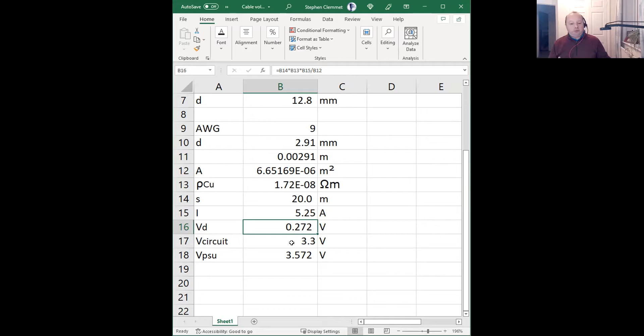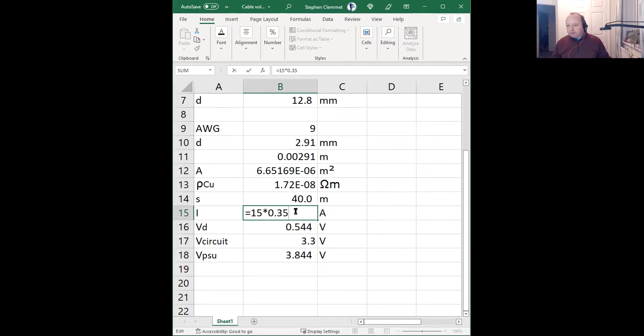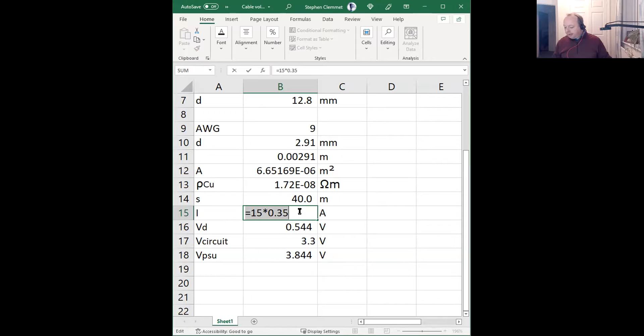And so look, we can just see here, if we make this 40 meters - make that 40, fingers crossed - things start to get a little bit more ugly. If we up the current... what have I done there? Oh right, that's something else, I remember that now - just experimenting with it. Yeah, if I up the cable to say 30 amps, then the longer the cable and the more voltage and current we want to put down it, you can intuitively see the voltage drop is going to get larger and larger.